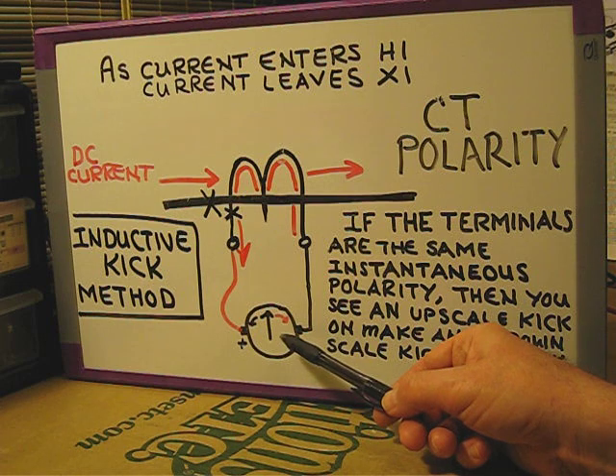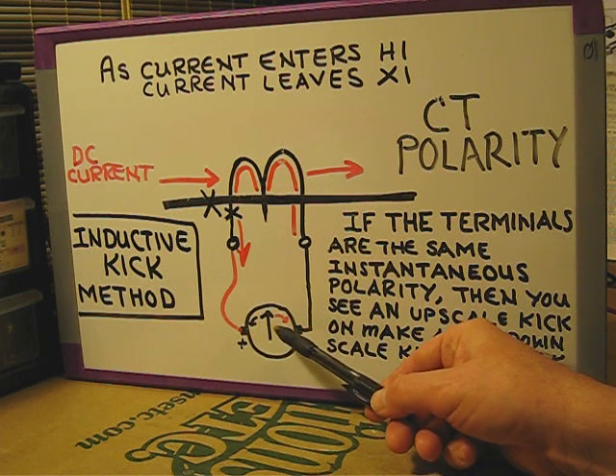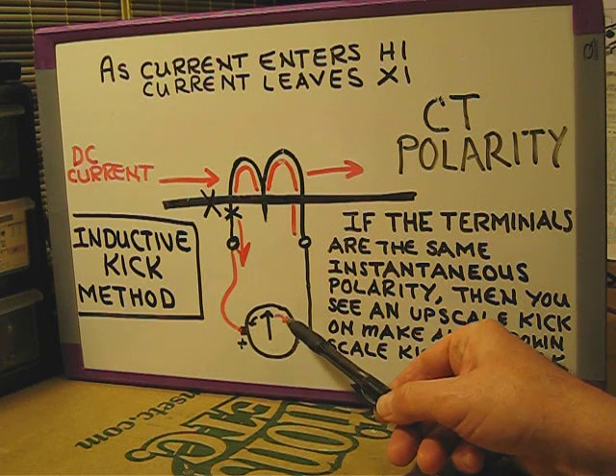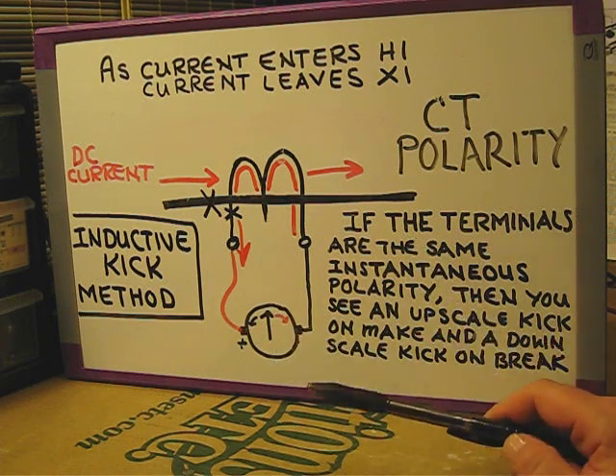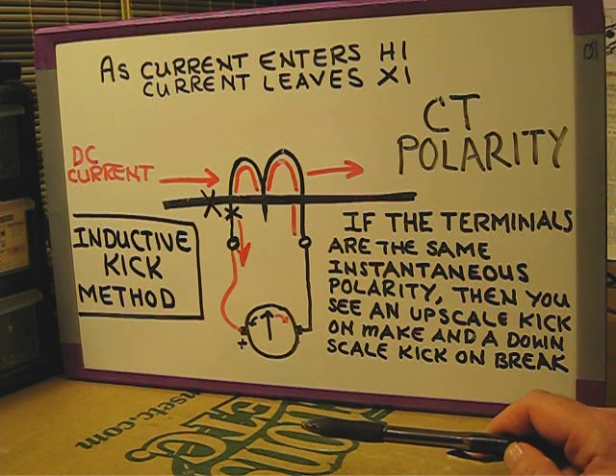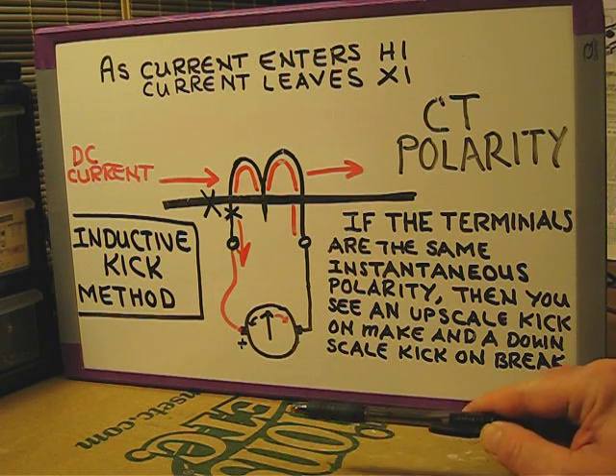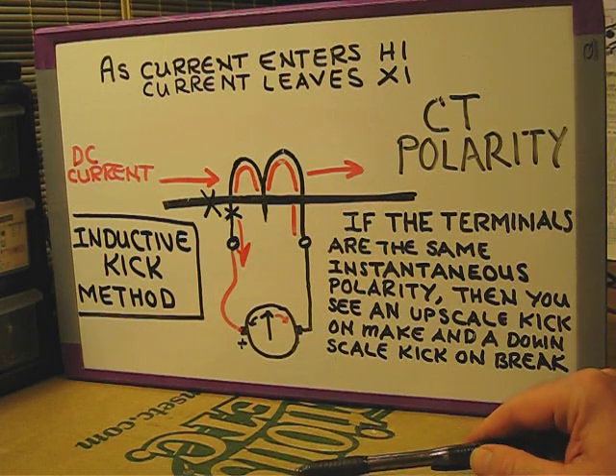To measure, we'll be using a DC milliamp meter with a zero center scale so that the needle can swing to the left or to the right. If the terminals are the same instantaneous polarity, then you will see an upscale kick when we make the DC circuit and a downscale kick when we break the DC circuit.